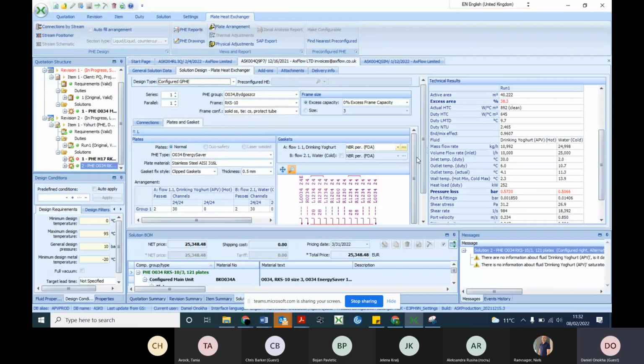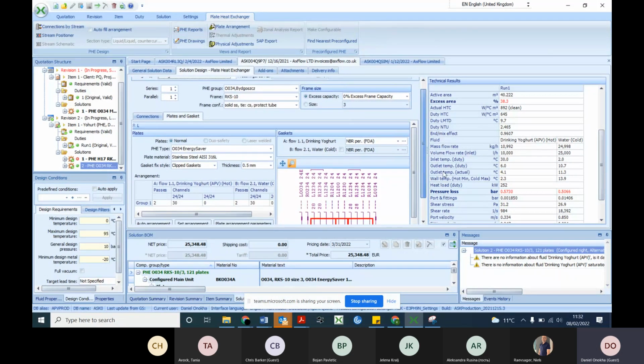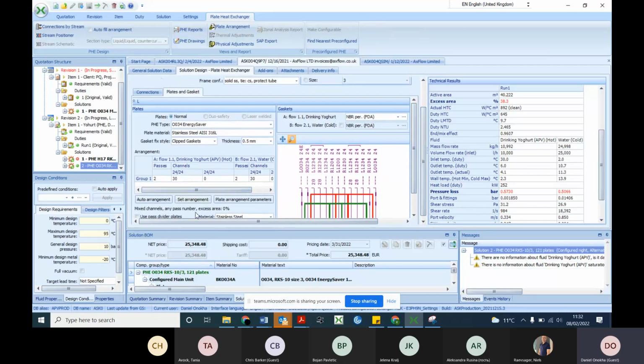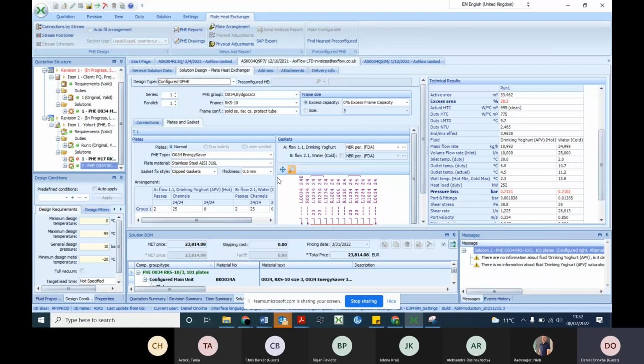Okay, that changed dramatically, the pressure drop. You see, it went from about 1 bar down to 0.5. You still have a lot of excess area, 38%, so you could decrease that. You can see now it's coming up with reasonable guidance, now it says 2 of 25. Before, with the other product, it said 1 of 1,000. You understand? Yep.